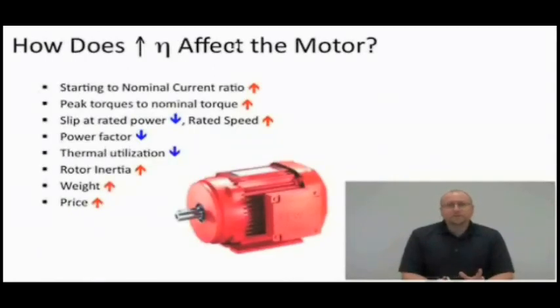So how does increasing the efficiency affect a motor? Well, a couple of different things. If you use copper instead of aluminum, it's going to be heavier. Copper is heavier than aluminum. So the rotor inertia goes up, and copper is more expensive than aluminum, so the price is going to go up. The rotor inertia is also going to go up with an over-dimensioned motor because inertia is actually more affected by the size and shape of a component rather than the mass, because the size has a squared effect on the inertia.